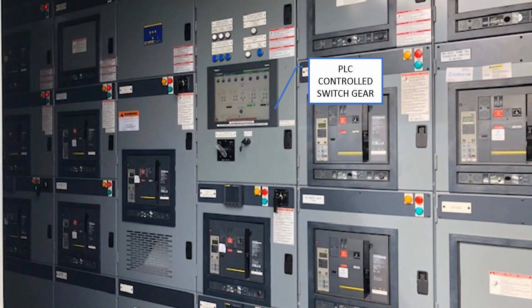The electronics in the switchgear is very complex. It is PLC controlled and is ultimately necessary to make sure that the quality of power that those engines are producing is able to be synced with utility. It's also making sure that the power is distributed where it needs to be and that it cannot go back out onto the grid during an outage. So there's a lot of critical operation happening here. We do monitor our output at our SCADA system, and with a max production capacity from the engines of 460 kilowatts, there are times where we're actually exporting power out to the grid.